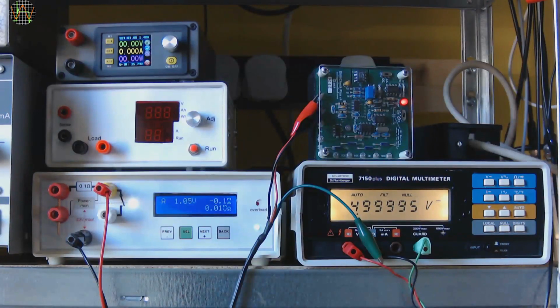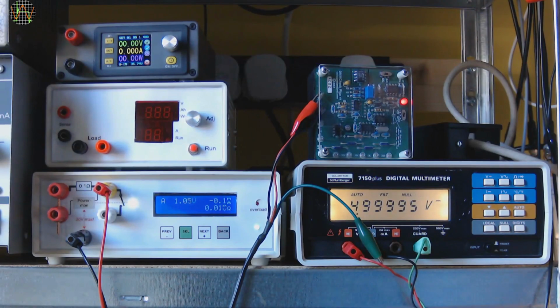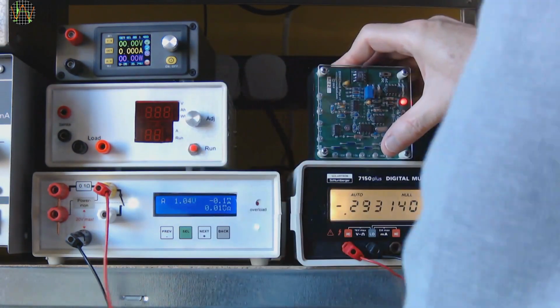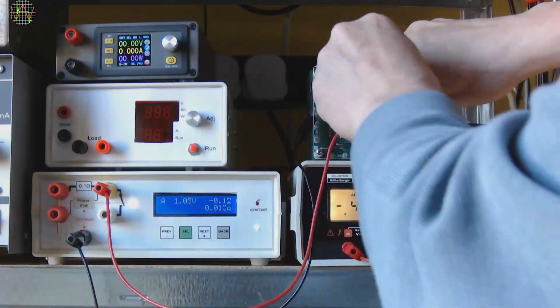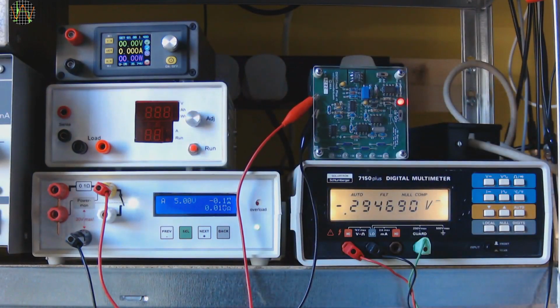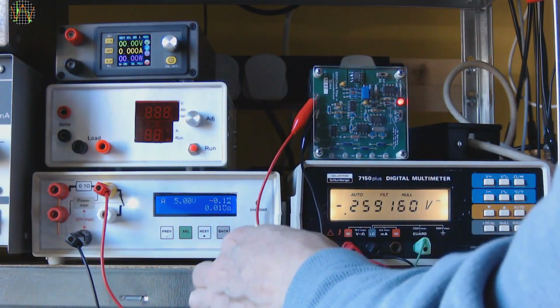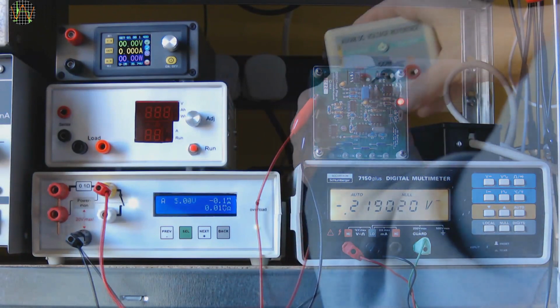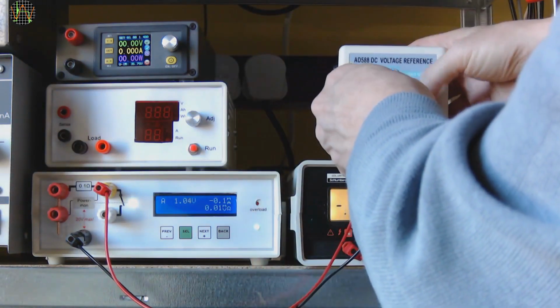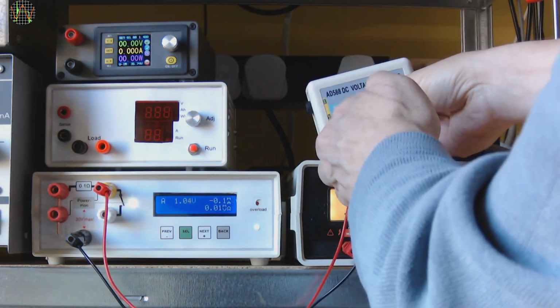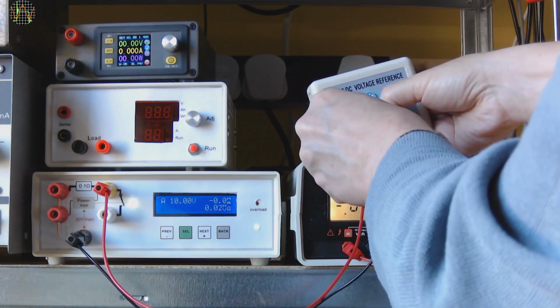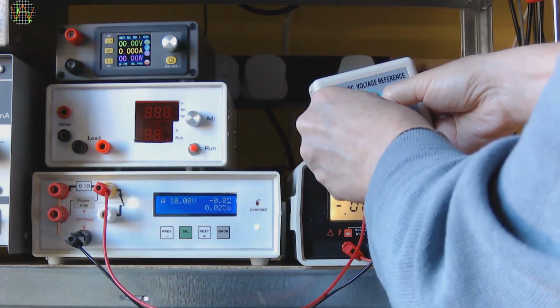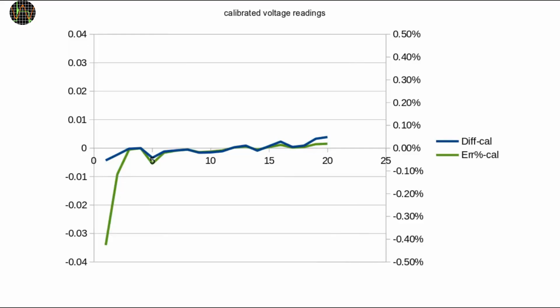Just for good measure, let's test it against my reference standards. First against the 5 volt output of the DMM Check Plus. 5.00 volts as expected. And the 10 volt output of my AD588 reference standard shows us exactly 10.00 volts. As you can see, the bus voltage calibration worked and produced excellent results.